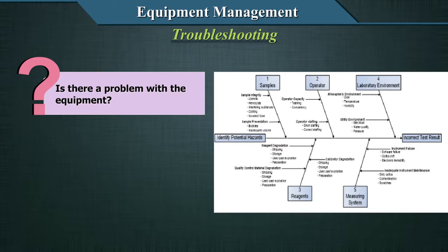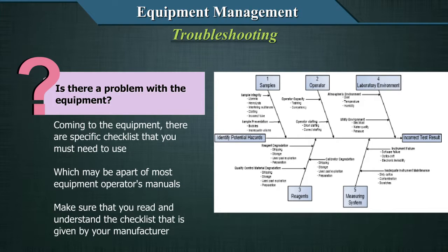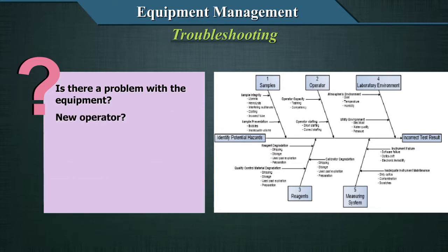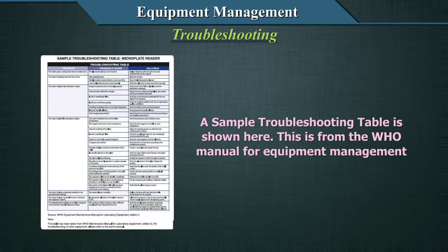Is there a problem with the equipment? Coming to the equipment, there are specific checklists that you may need to use, which will be part of most equipment operators' manuals. Make sure that you read and understand the checklist that is given by your manufacturer. One more thing to look at is whether it is a new operator — somebody not trained. A sample troubleshooting table is shown here, from the WHO manual for equipment management.